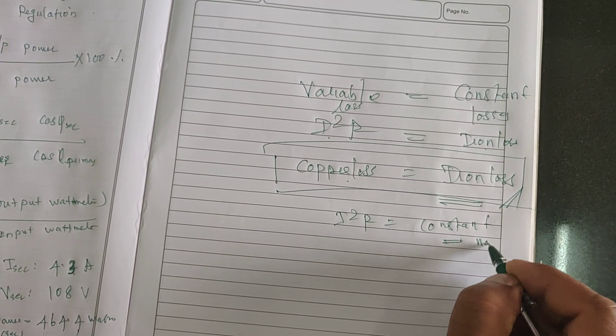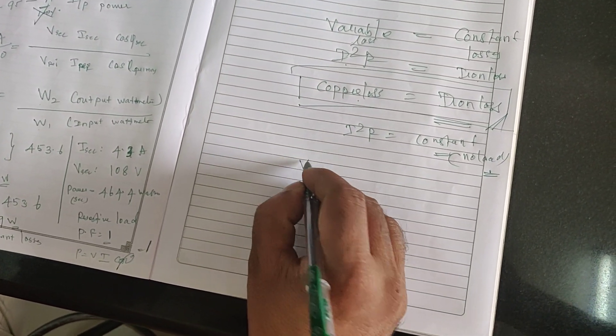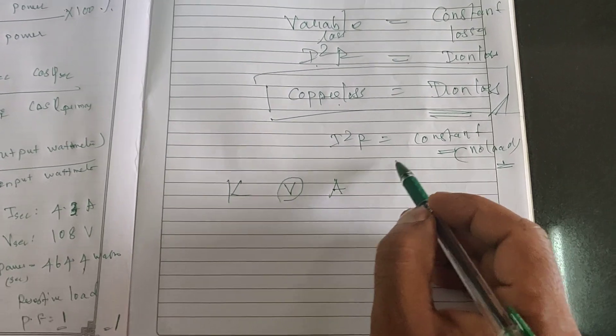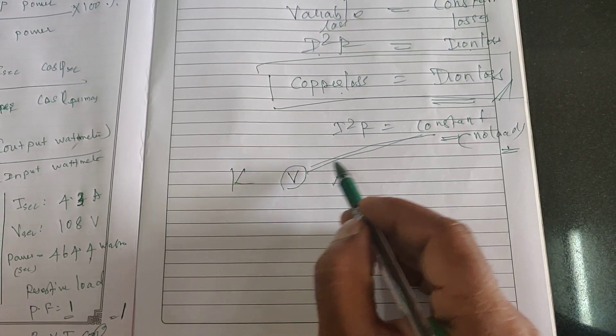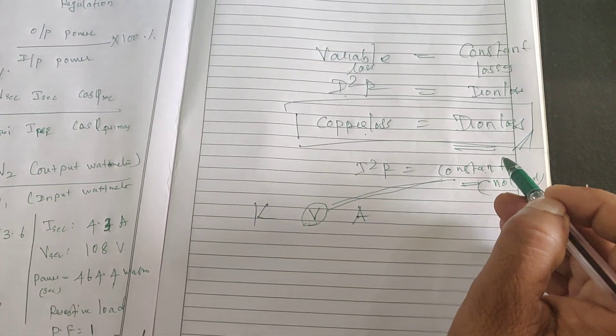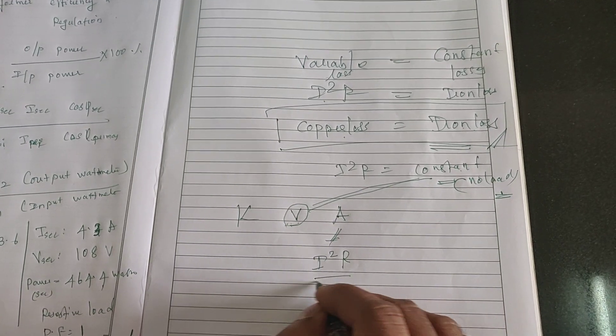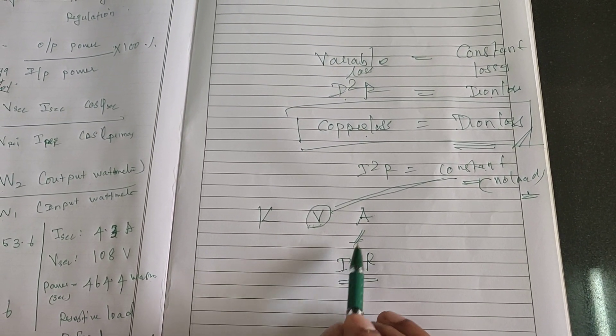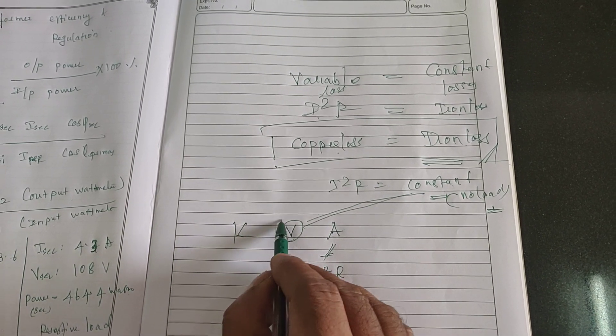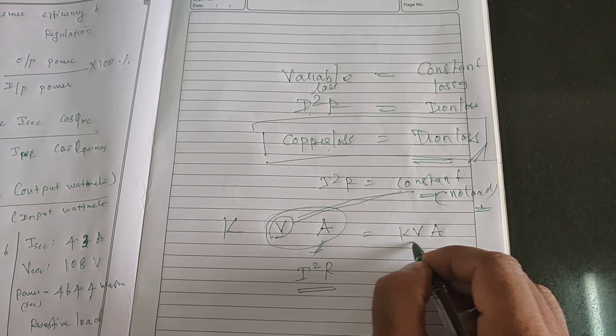And I told you — why is a transformer rated in kVA? In kVA, V stands for voltage and A stands for current. The iron loss is governed by the voltage, which is the main parameter contributing to constant (iron) losses. The I²R (copper) loss is governed by the current (amperes). Therefore, the losses in the transformer are decided by two components — voltage and current — and so it is rated in kVA.